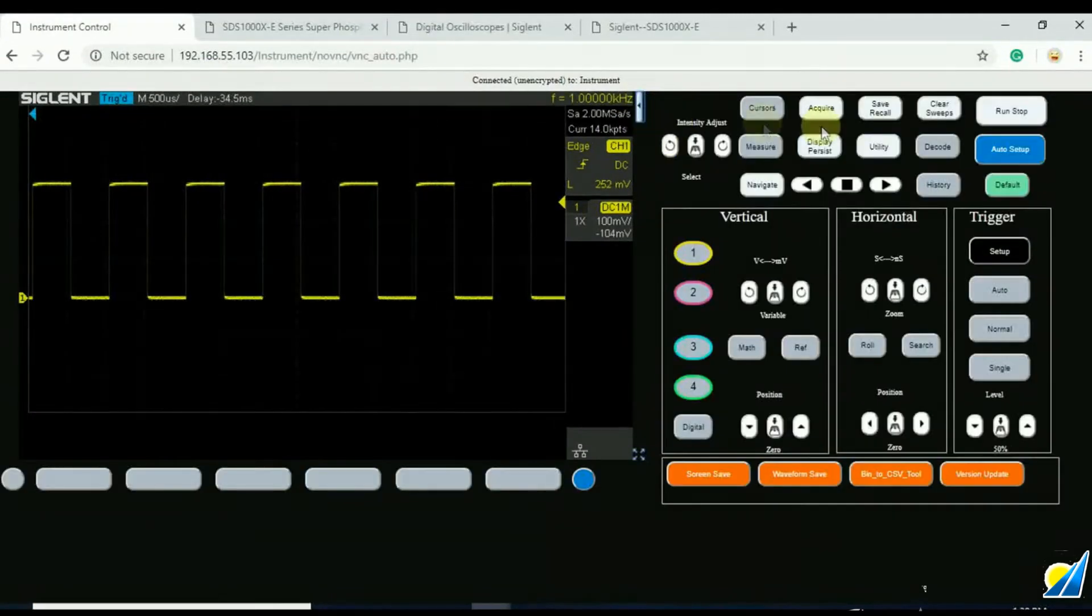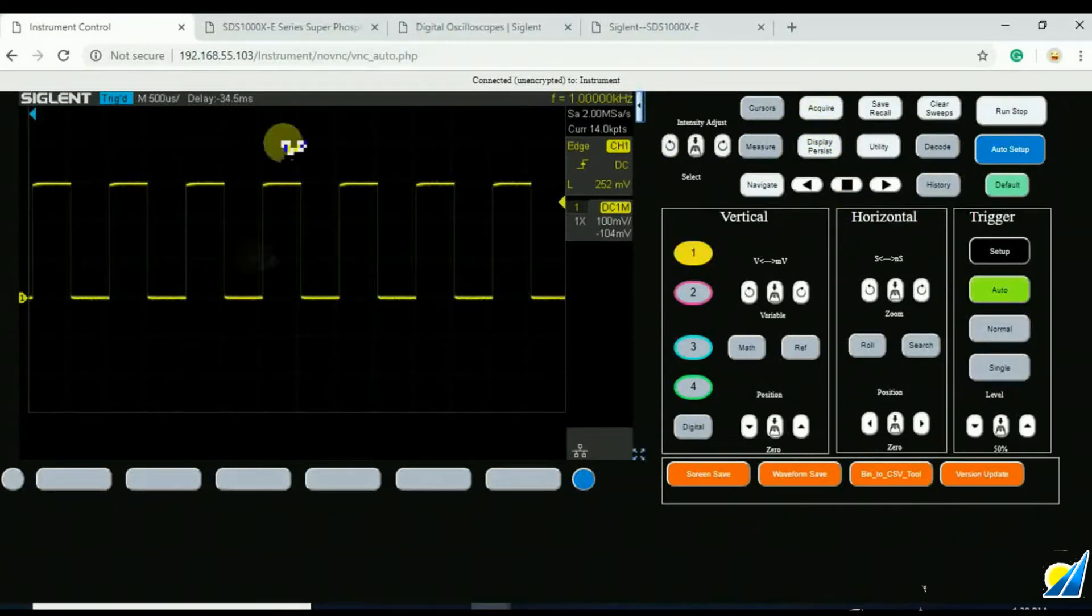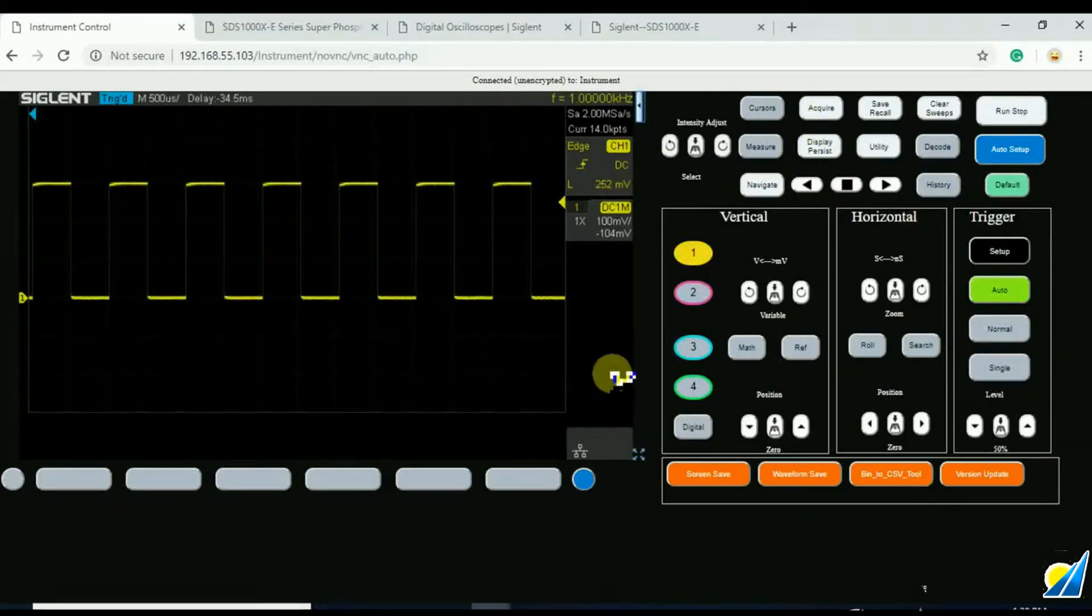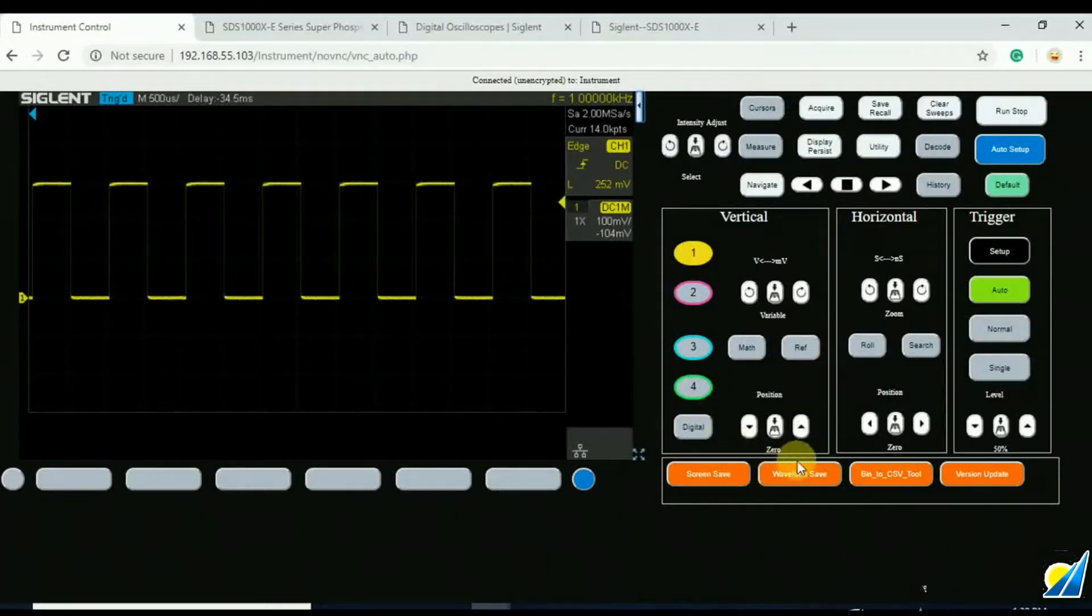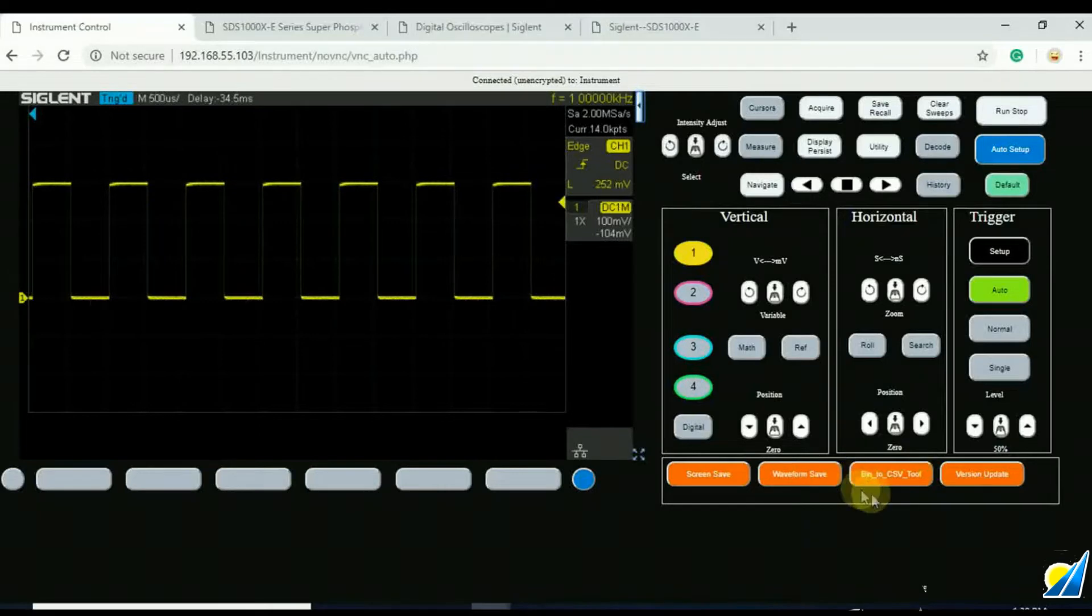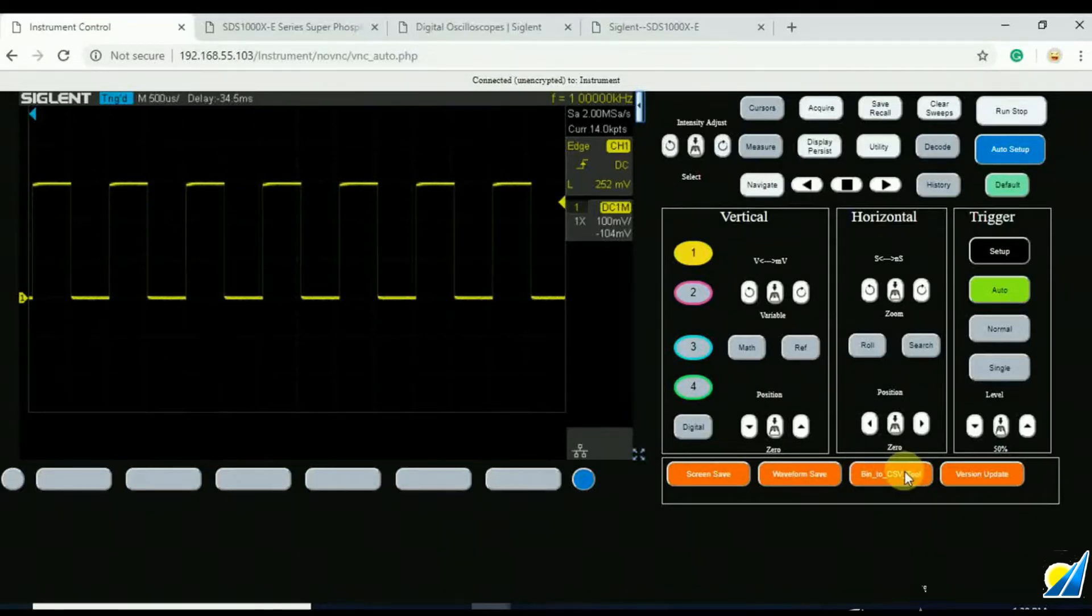Nothing too new here if you've seen the other videos about the web control on the 4-channel X-E. But what you will notice is now we've got a binary to CSV tool here. So we can download that from the instrument itself.